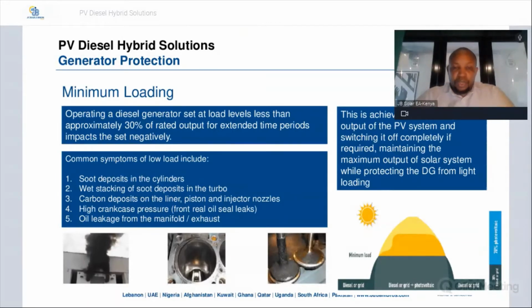And this is usually seen in the form of soot deposits in the cylinder. You have wet stacking of soot deposits in the turbo, as well as carbon deposits in the liner, piston, and injector nozzles, as well as high crankcase pressure, front and rear oil seal leaks, as well as oil leakage from the manifold and exhaust. So operating your generator below the minimum loading rate will reduce the lifetime of your generator. So how do we protect the generator from minimum loading?